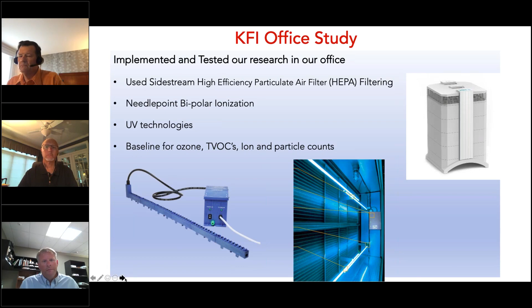So what we've learned, obviously, do the research. Not all new technology has been tested. Not all equipment's the same. You know, we've tested 4 different types of bipolar ionization, all different results. Tested in the same heat pump and serving the same room. Some systems produced ozone, some didn't. So it's really understanding the differences between equipment. Every equipment manufacturer will state that their equipment's the best, that they've been third-party verified. I just had 2 emails today from equipment vendors saying, yep, we passed the UL testing for production of ozone, which UL's listing still lets them produce some ozone, but those are things that we want owners to understand.